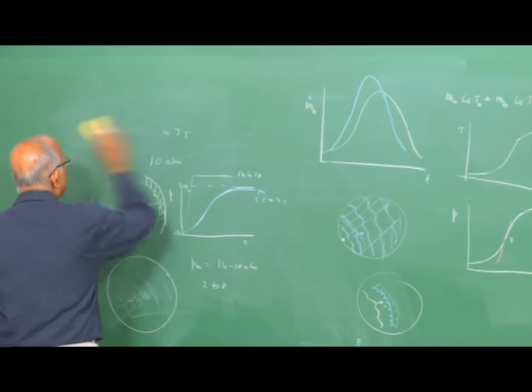Therefore, to summarize at this point, we have estimated the maximum pressure in a constant volume explosion, namely PM. We have also estimated the value of dP by dt maximum, and this we find is equal to K_G divided by V to the 1/3. K_G is a constant for a particular gas, having the same turbulence level, ignition source being similar and the geometry being similar. Values of this are available in literature. Using this I can find out for a given volume what is the severity or the rate of pressure rise in an explosion.